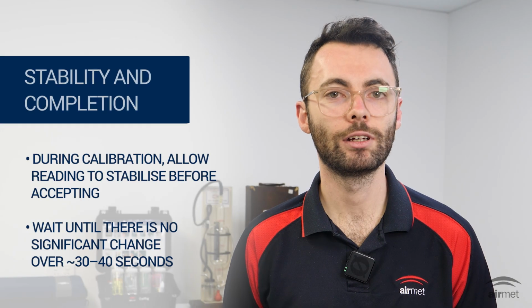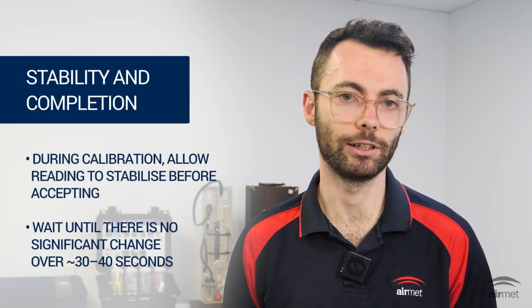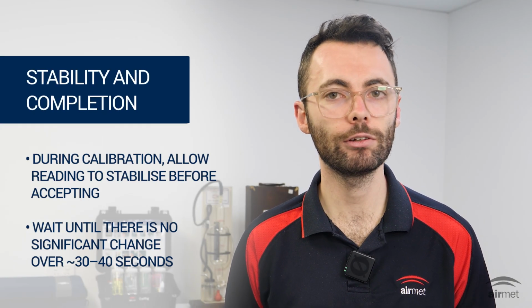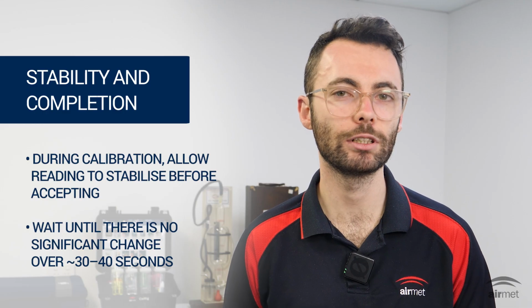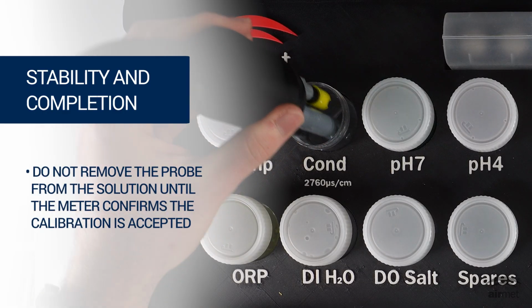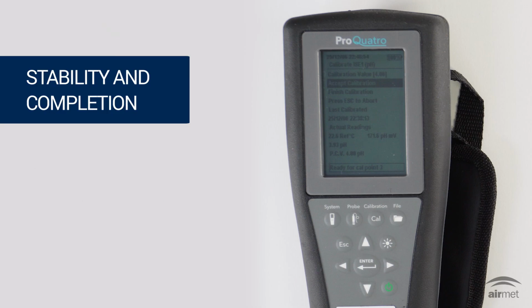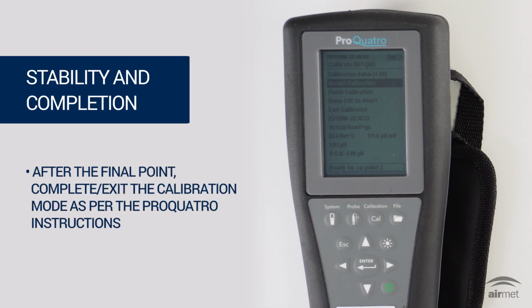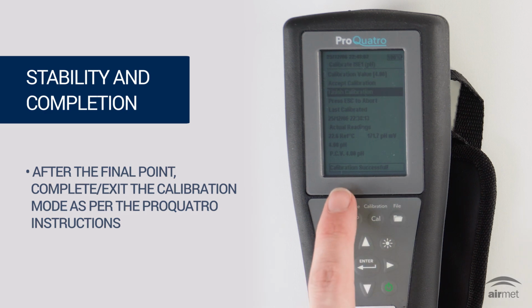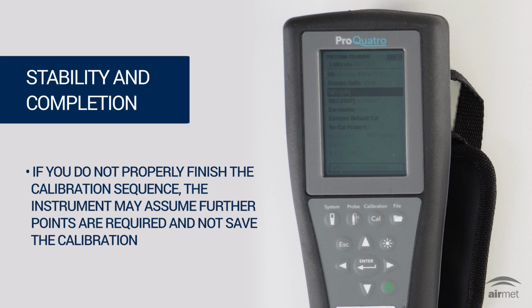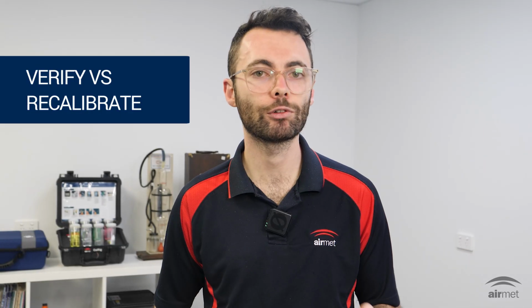During calibration, allow the readings to stabilize before accepting. As a rule of thumb, wait until there is no significant change over about 30 to 40 seconds. Do not remove the probe from the solution until after the meter confirms calibration is accepted. After the final calibration point, complete and exit the calibration mode as per the ProQuatro instructions, for example, finish calibration or return to measurement mode. If you do not properly finish the calibration sequence, the instrument may assume further points are required and will not save the calibration.